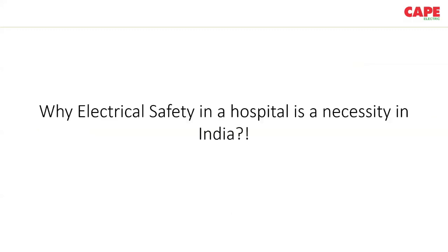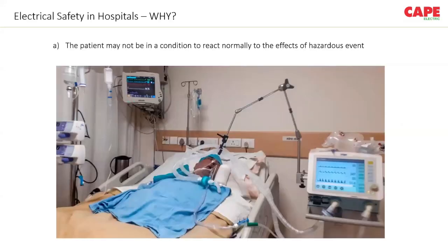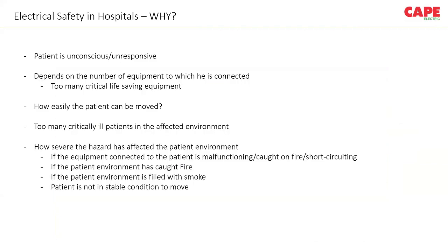So the question is, why is electrical safety a necessity in a hospital? Answer, the reason number one, the patient may not be in a condition to react normally to the effects of the hazards. The type of the patient matters. Patient can be an unconscious patient. The patient can be an unresponsive patient. So it will depend upon whether we'll be able to move the patient from one location to another if a hazard is happening. We cannot wait for the hazard to go away to move the patient, right? We'll have to move the patient then and there.